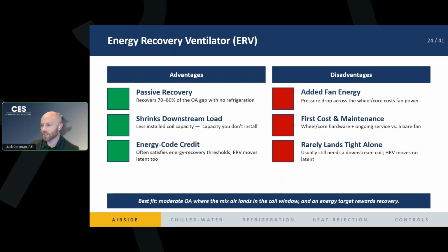But the disadvantages are that you have some fan energy, right? You're going to have pressure drops. You have to run your exhaust air through this ERV, so that adds a pressure drop that you didn't have if you just dumped it out through a louver. Potentially in a large building with high CFMs, that could be significant in operational costs. This is a higher first cost than the outside air fan, but it is lower first cost than the DOAS system. So it is really just comparing whatever options are available for you. You're going to have some maintenance with your energy recovery wheel, potentially, just more points of failure than just having a duct go through a fan, pull the air through the duct.